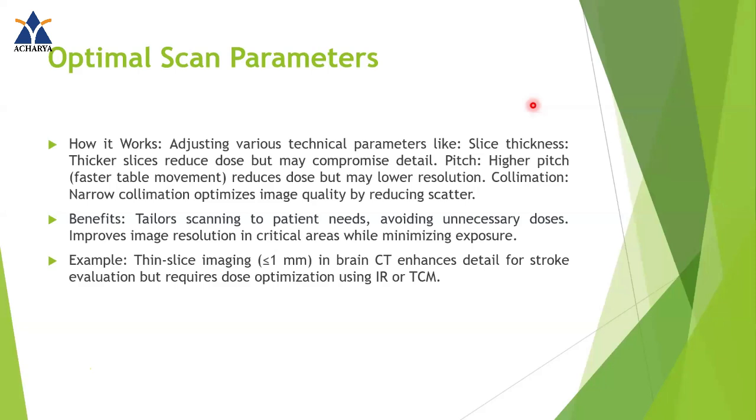Pitch again, pitch is the table movement per rotation of the gantry. So higher pitch means faster table movement, which reduces the radiation dose to the patient. But when the faster table movement happens, it reduces the resolution of the images.